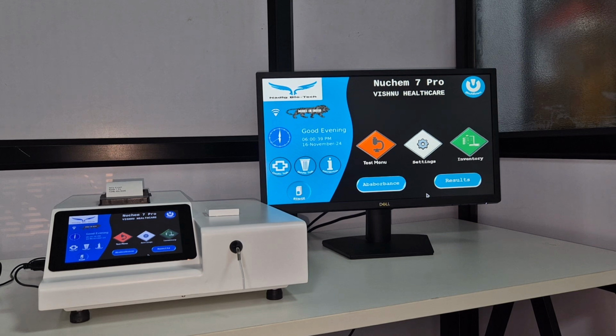And for kinetics, this is the first time it supports multi-standard by kinetics, which is mainly used in R&D laboratories. Apart from that, it has 6 filters from the range of 340 to 630 nanometers. It has a 6 volt halogen bulb, long lasting, more than 1500 hours. So practically it would last more than a year. And some of the other features, the mundane features, are that it supports 1000 plus test program memory and 1 lakh plus result storage area.